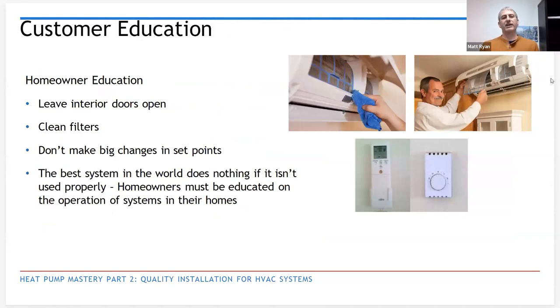This one, I owe Bruce credit on this one. I'm not the best when it comes to soft skills, but when you're all said and done, going over things with the homeowner. If we're trying to accomplish heating and cooling throughout the house with cassettes, making sure interior doors are open. Even in retrofit, usually with new ductwork, we usually have better setups, better systems for the interior door debate, but it's good practice to leave them open when possible. Making sure they know that they have filters that need to be cleaned, showing them where and how to clean those filters. This is a big one here: don't make big changes in set points.